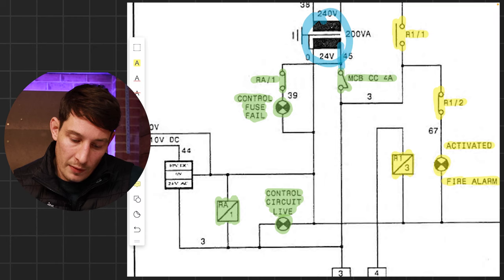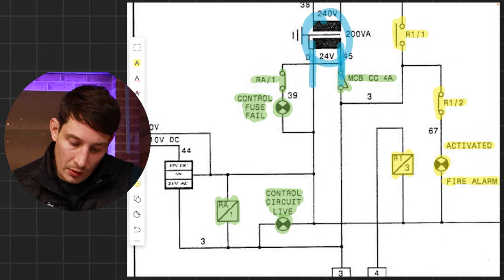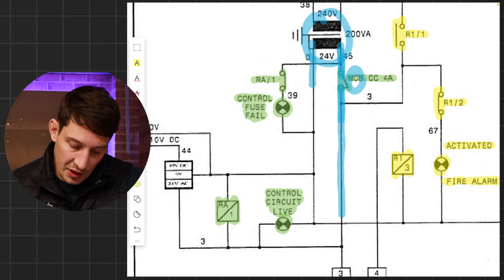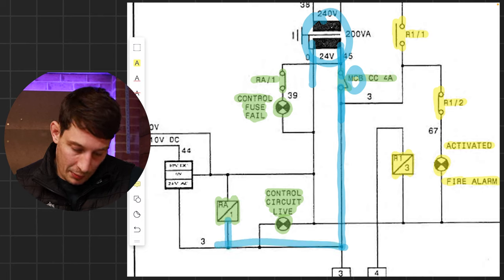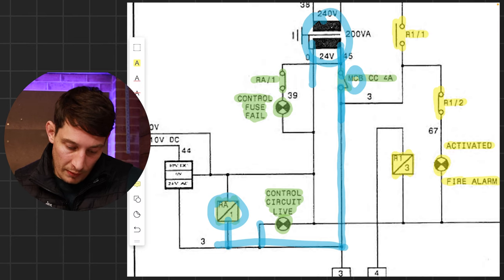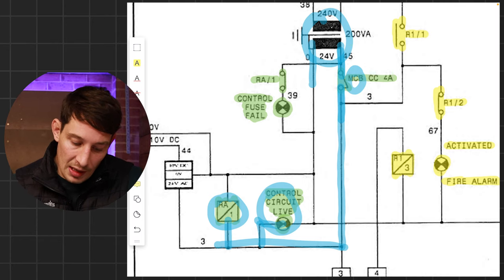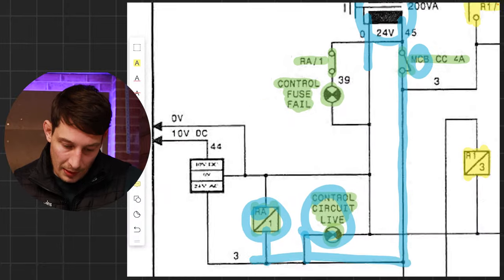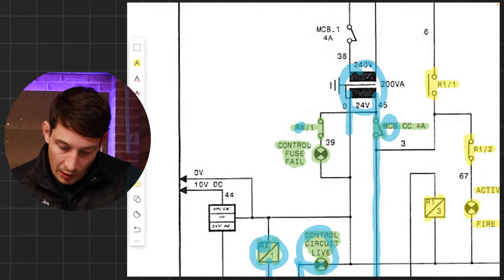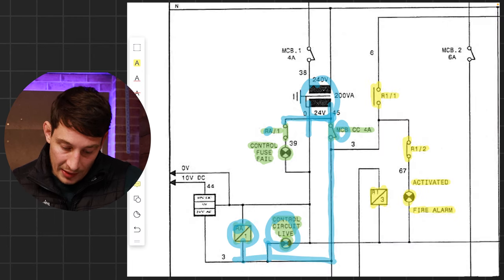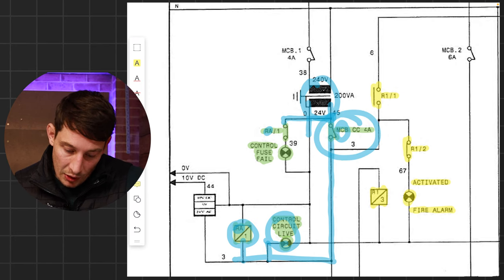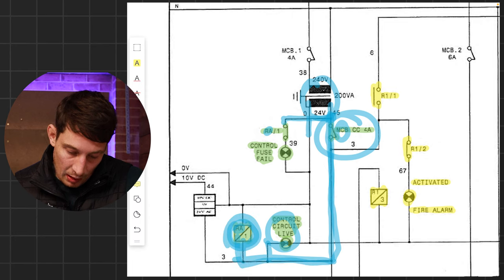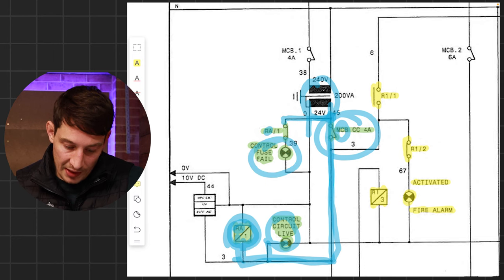Let's start with the green components. In a nutshell, this little subsystem ultimately protects the 24 volt AC circuit and indicates if the control circuit is live or the fuse has tripped. We've got our transformer — 24 volts on this side, 0 volts on this side. If everything's good with the fuse — this MCB, it's actually a fuse — the voltage can travel down here, and two things happen at once: relay RA energizes at the coil, and the control circuit live lamp lights up. This is a normally closed contact, so when that MCB is good it's closed and energizes RA, which then opens the normally closed contact, not lighting the control fuse fail indicator.